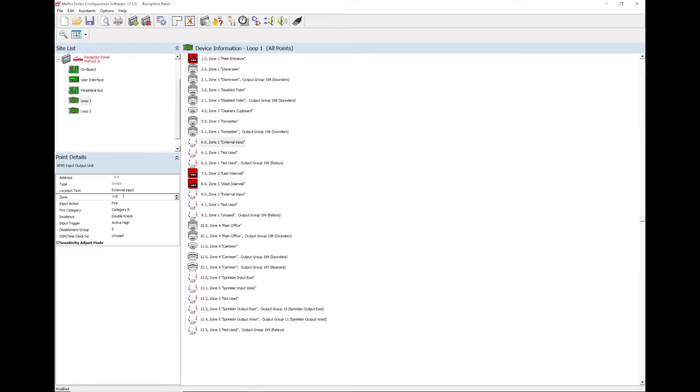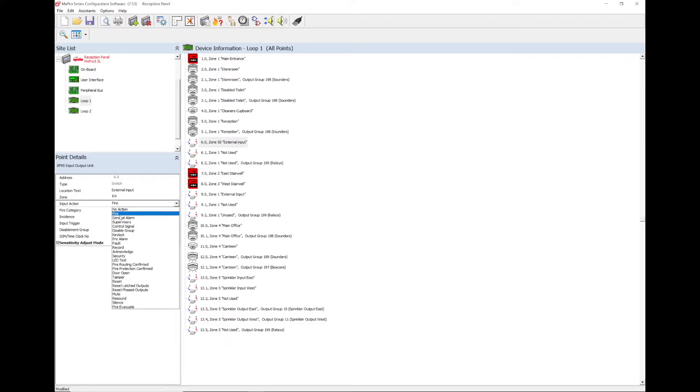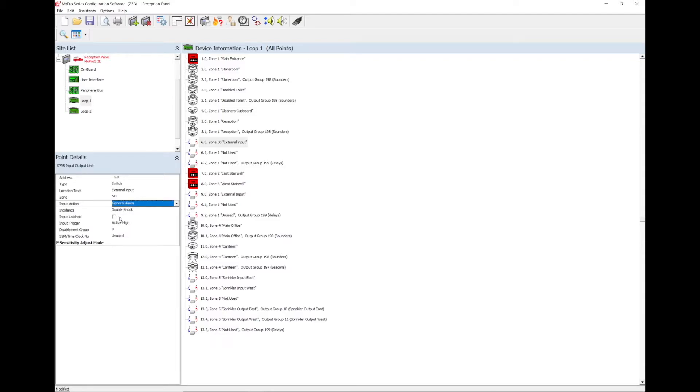The input action should be set to general alarm so that it does not show on the panel as a fire signal and cause confusion. Instead, it will show as an alarm condition. Ensure that the input latched option is unticked so that when the input is no longer active, the panel automatically resets and turns off the sounders.